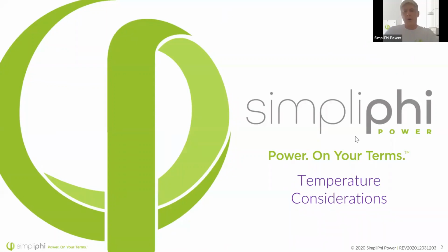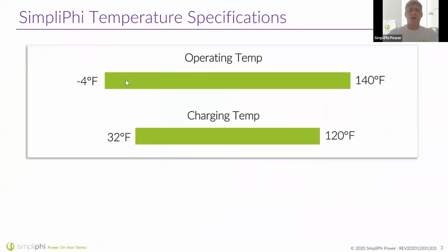First, we're going to talk about temperature considerations. We have our operating temperature range from -4 degrees Fahrenheit to 140 degrees Fahrenheit. This applies whether discharging or simply in standby mode, stationary, turned off, not powering any load. As far as charging temperatures, SimpliPhi batteries can be charged between 32 degrees Fahrenheit, freezing temperature, and 120 degrees Fahrenheit. This is a really wide window.